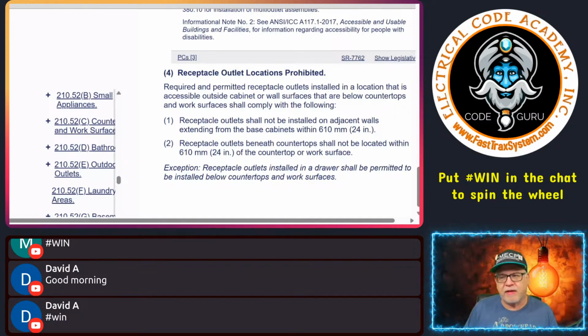So the listed HVAC equipment had this exception that went up to September 1st, 2026. The code panel wanted to keep it at 2026. The NITMAM wanted to move it to September 1st, 2029. The manufacturer said there's a problem. They know there's a problem with the GFCIs and being able to do this. The GFCI manufacturers said no, we have what's called a special purpose. It'll work fine. It's a 20 milliamp. You can't exceed that. And so it won't have those high trip frequencies, especially during the compressor startup. They said, we got this, right?